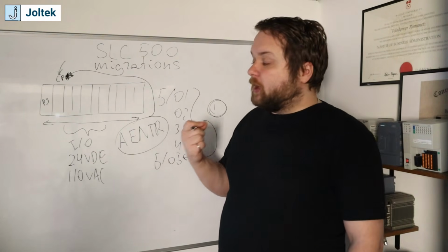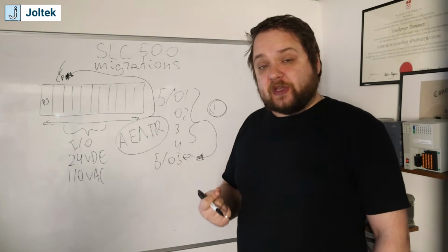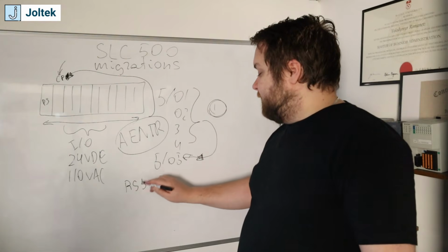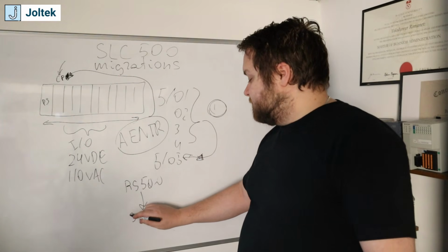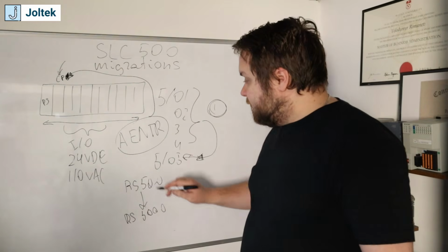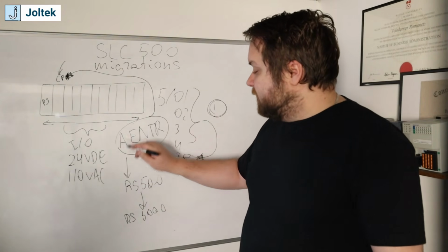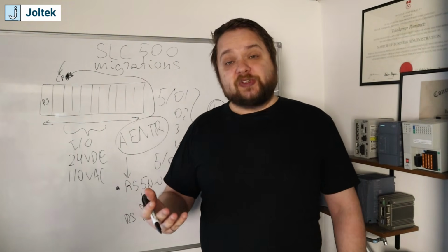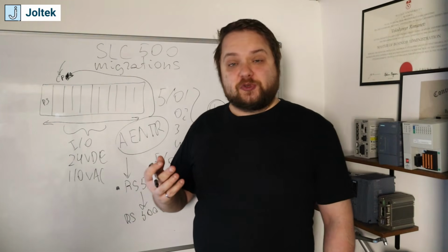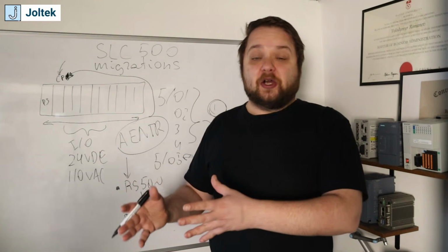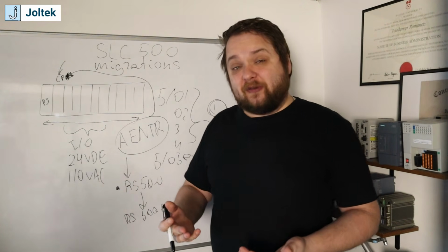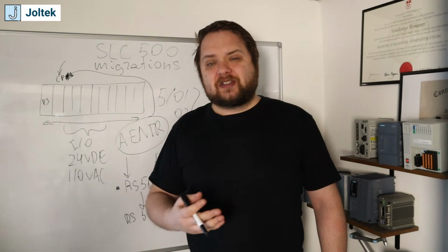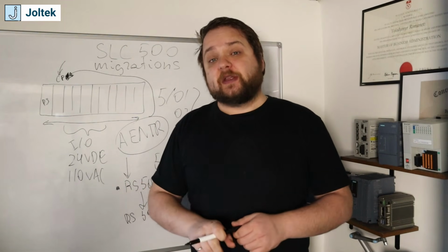And so the only possibility of doing this is if you convert the program from RSLogix 500 to RSLogix or Studio 5000. So this is the requirement for this specific migration. And you can use the conversion tool. There is a Rockwell built conversion tool that allows you to move RSLogix 500 into RSLogix or Studio 5000, which makes it easier, but I would say it is not always ideal. So there is some massaging of the code required to make this happen.